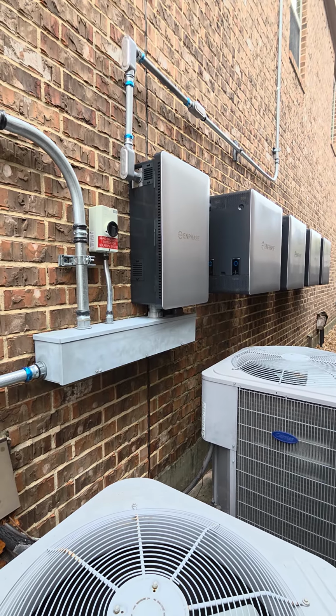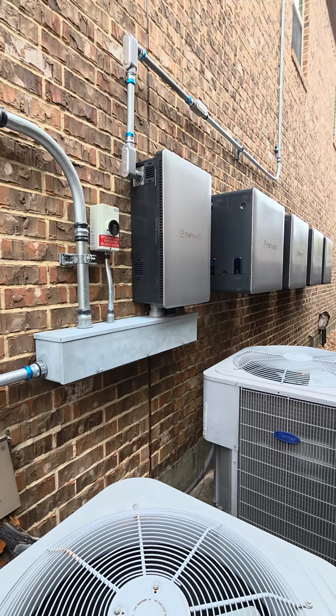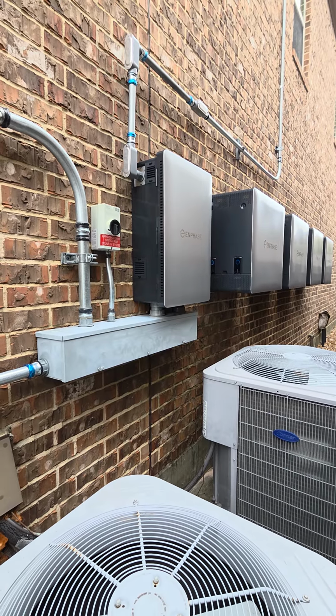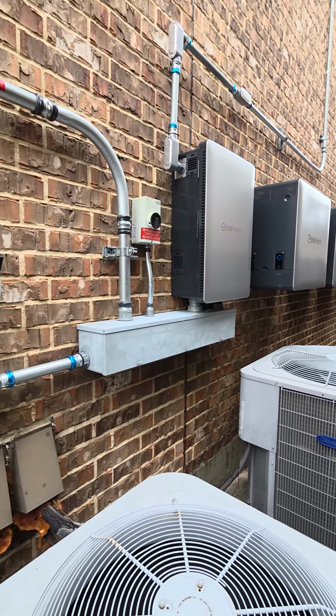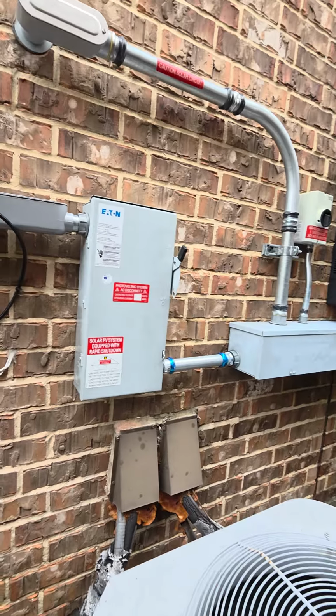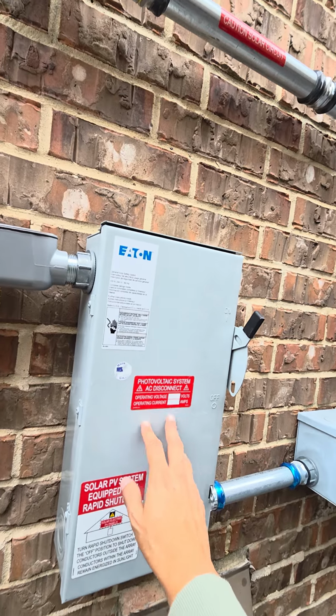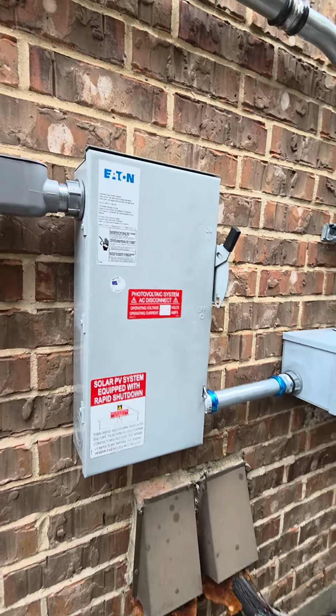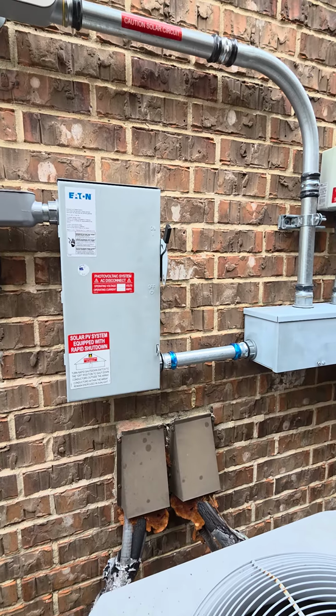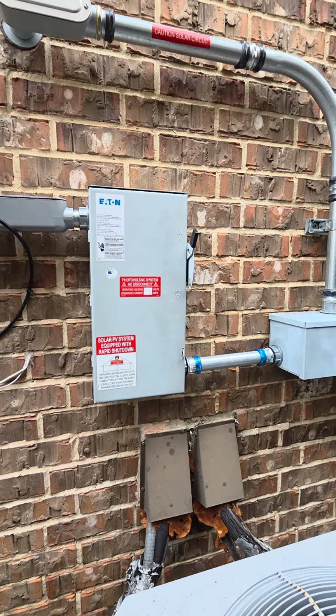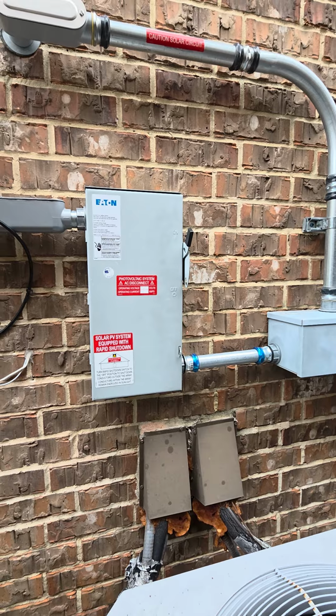Which I'm actually pretty happy with. The Combiner 6C is so much better than the 3rd gen system controller and combiner, which were two separate pieces of equipment. Anyways, I kept the grid disconnect from my previous install. I had to move it, obviously, and it's a 2-pole, while the Combiner 6C recommends a 3-pole for their AC sense disconnect.